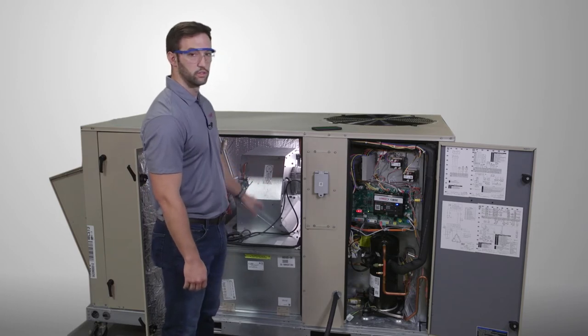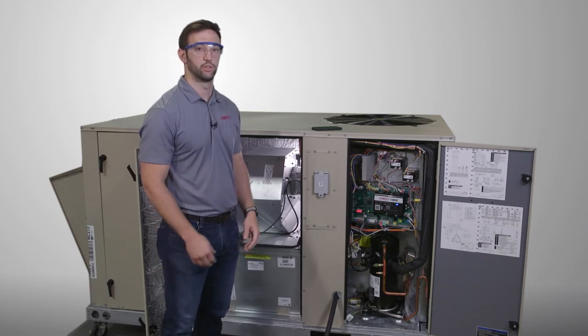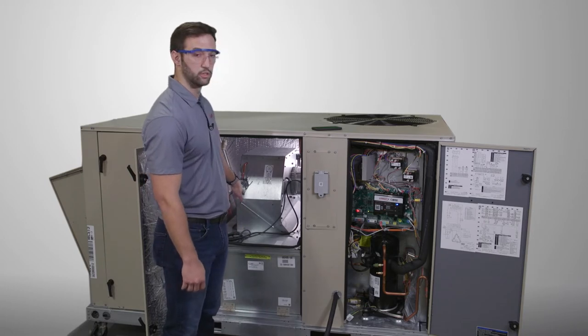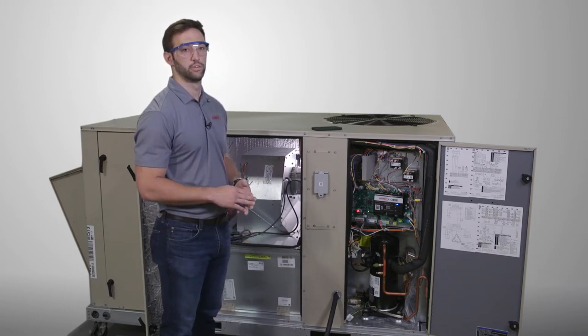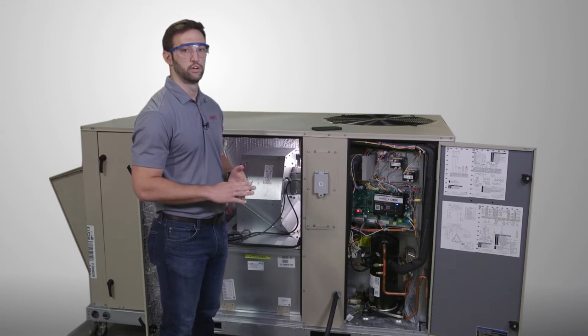Our indoor blower will be operating to maintain a saturated suction temperature, which is basically the evaporator coil temperature. It is going to try and optimize the airflow so that we're removing as much moisture as possible from the air.